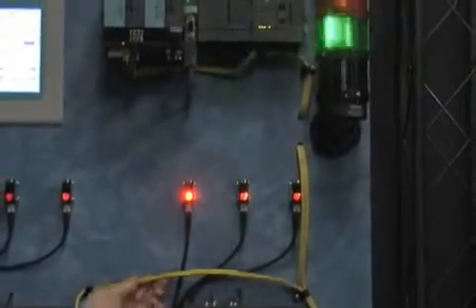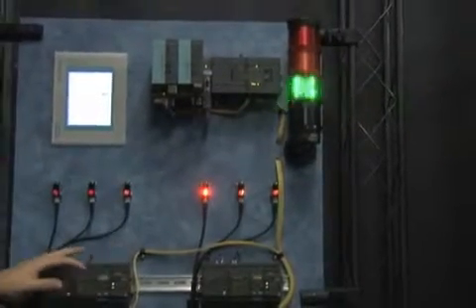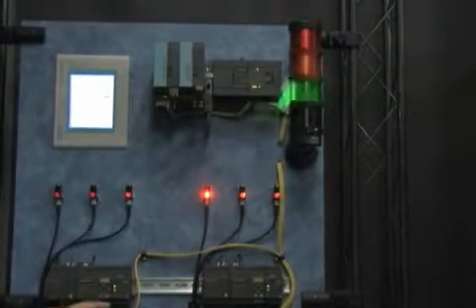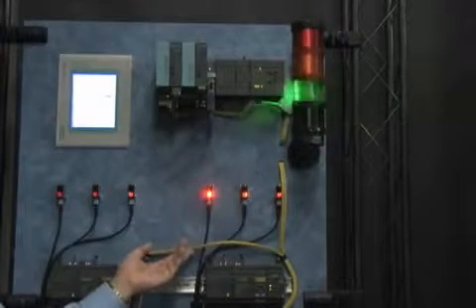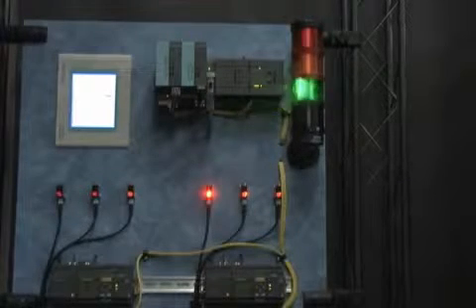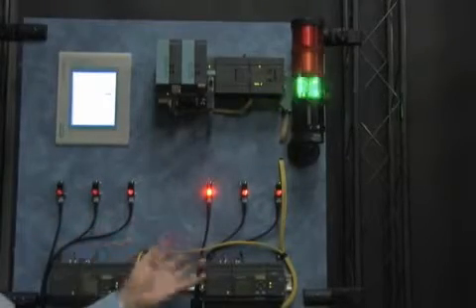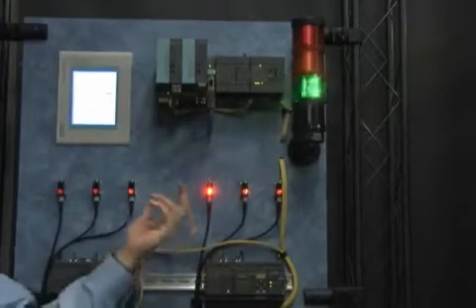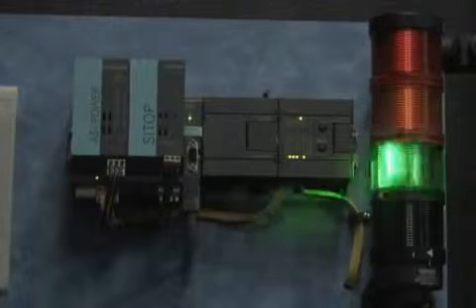is through our ASI interface network. ASI is a unique device level type of control system that eliminates a lot of wiring because it carries both power and signal over the same two-wire cable. You're able to get diagnostics when there's missing power or wires are off any of the devices, and you don't have this nest of conduit and termination of several signals to the upper level control system. This is all part of our Siemens totally integrated automation solution across all of our controllers and automation technology.